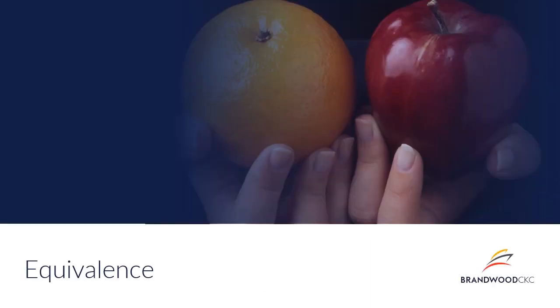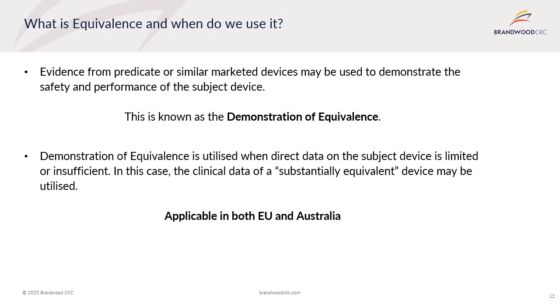Now, this leads us into our second item. So what is equivalence and when do we use it? When we talk about equivalence, we are specifically referring to evidence or data from a predicate or a similar marketed device that may be used to demonstrate the safety and performance of the subject device. This is needed when there isn't enough direct clinical data on the subject device.